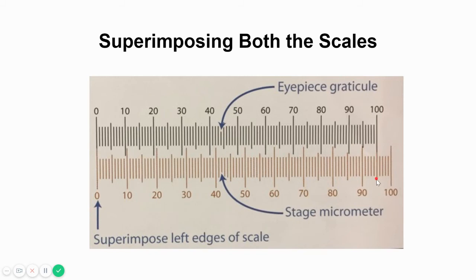Now the thing is, in our previous video, we had already calculated the length of the stage micrometer. So if I know the length of the stage micrometer, can I now calculate how much is the value of these 100 divisions of the eyepiece graticule? Yes, I can.